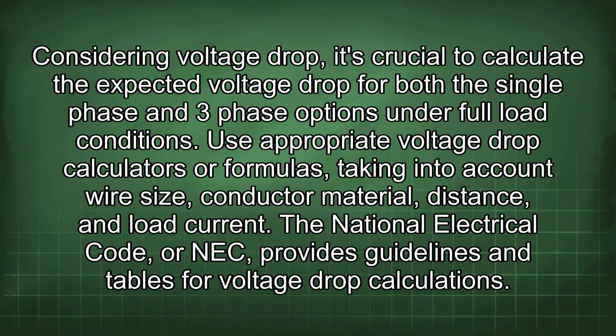Considering voltage drop, it's crucial to calculate the expected voltage drop for both the single-phase and three-phase options under full load conditions. Use appropriate voltage drop calculators or formulas, taking into account wire size, conductor material, distance, and load current. The National Electrical Code, or NEC, provides guidelines and tables for voltage drop calculations.